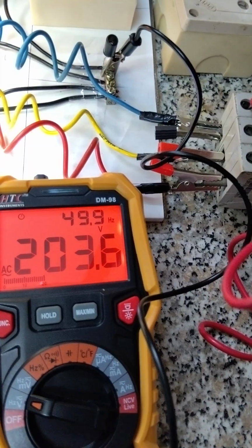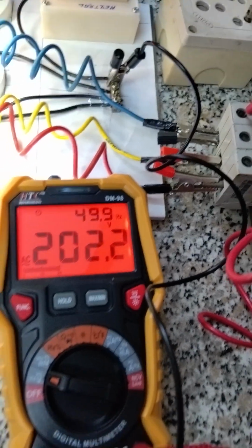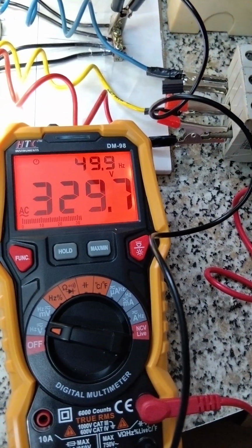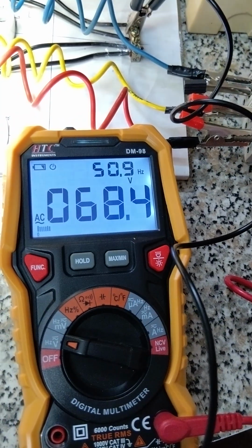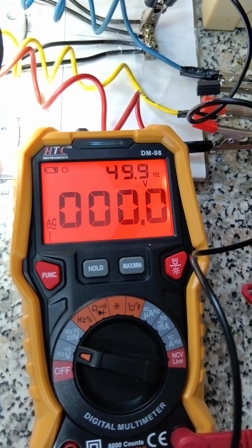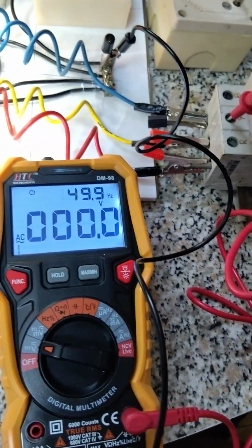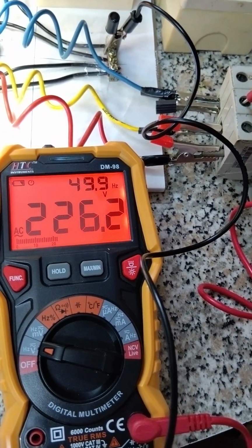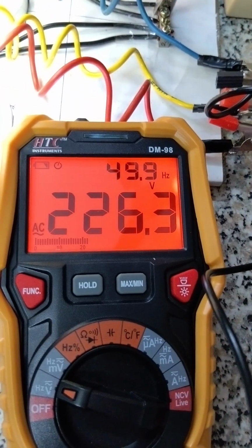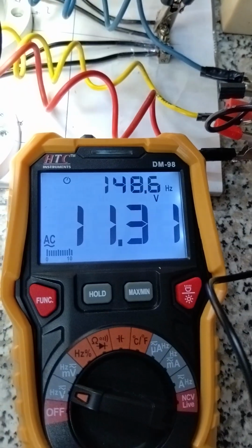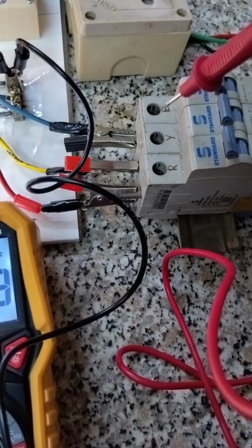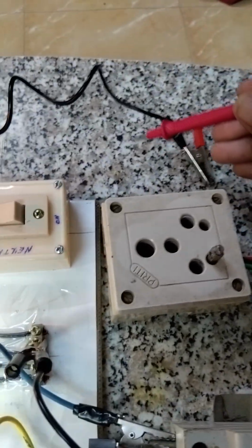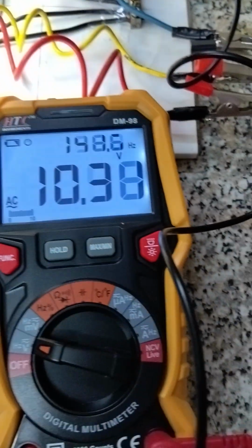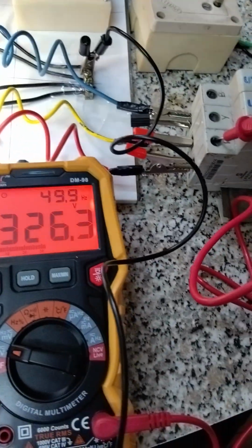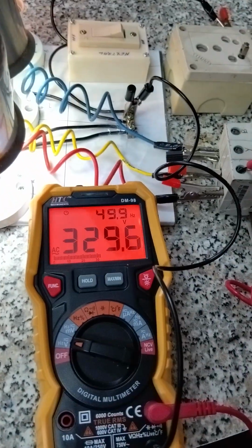See, note the difference. This is the lowest, and this is the highest, 330. So low voltage, high voltage and normal voltage. It depends upon the load and the voltage between the phases. It is looping between the phases because there's no return path. It is completely disconnected. The service neutral has been disconnected. So this is the important moment.